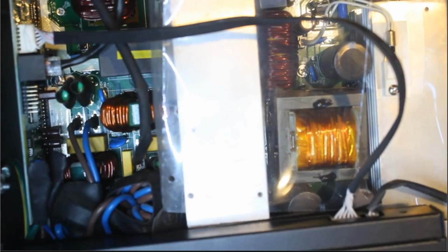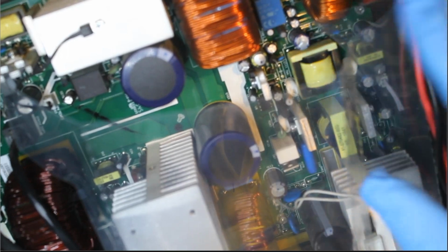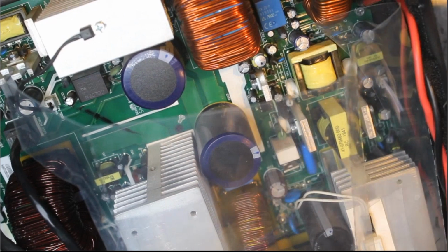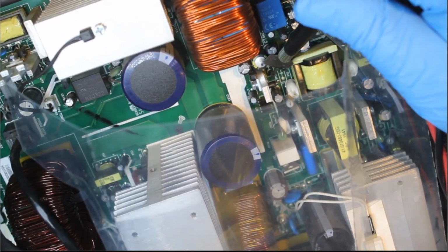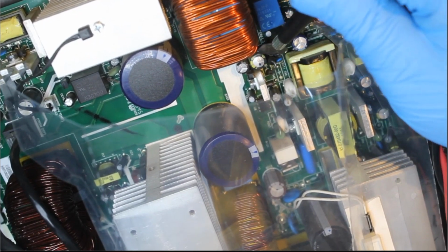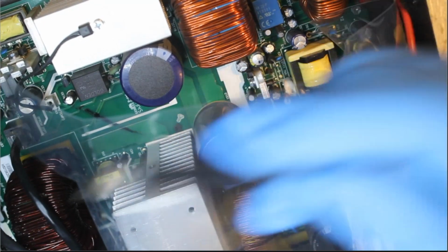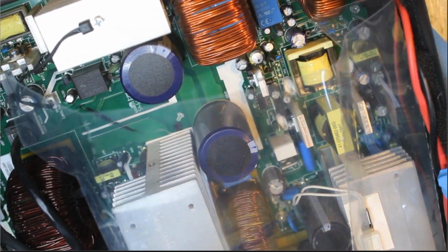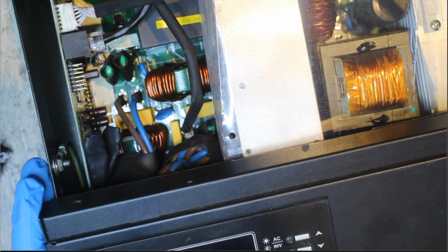And also, this inverter has got a damaged capacitor there. So when this capacitor gets damaged, it doesn't fail alone. That's why we're having that F09. So we have to also change all those capacitors. You can see this one, it's bulged. So we are going to change it, and also change the components around the circuit to make sure that the inverter is okay. So let's fix the inverter. I've already showed you, it's showing F09.